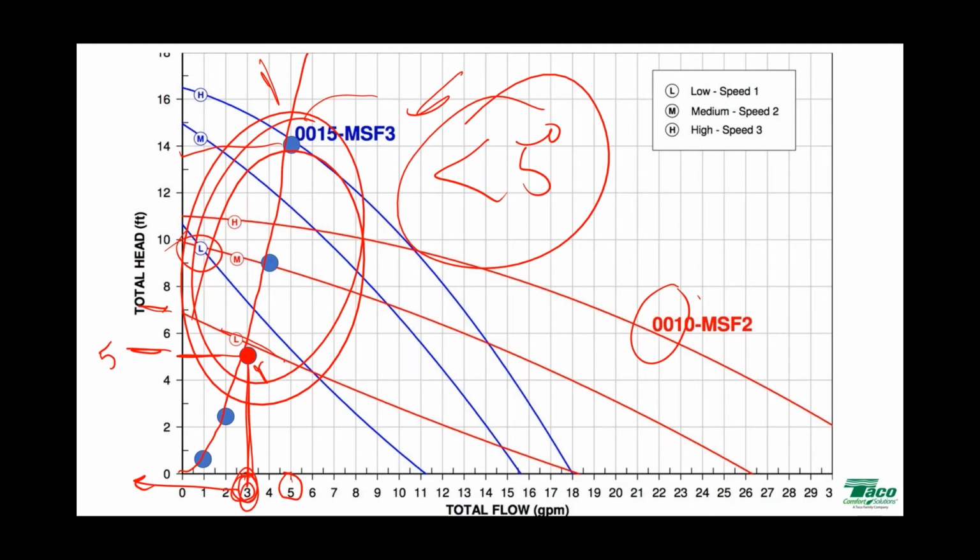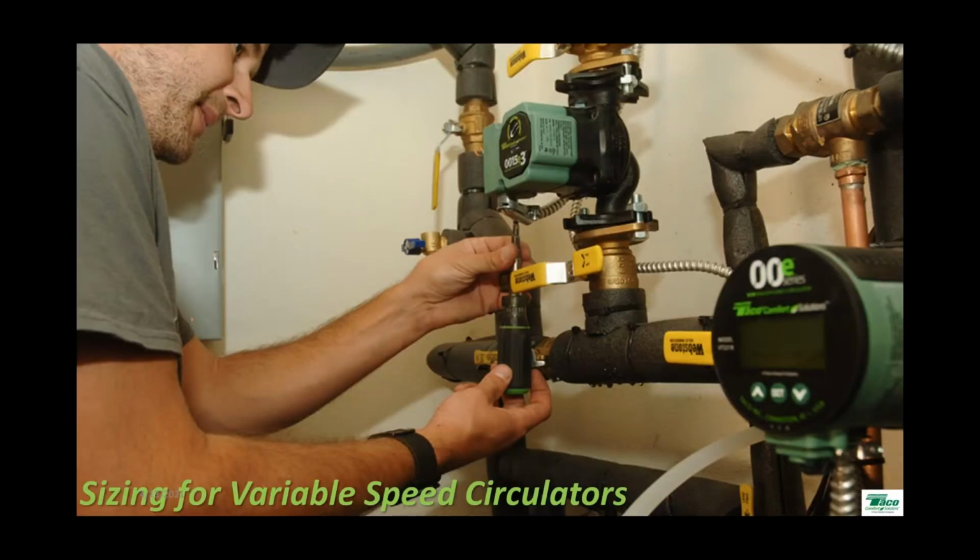And everything is true up until it comes to the point of choosing the circulator. Well, I use this circulator all the time because I get it for the best price and it's never failed me, and they always set them to high. So you're getting like 90% of the way there, and that last 10%, which is the most important 10%, we're basically not paying attention to. The circulator, as we said before, has more to say about the overall efficiency of the system and the long-term viability and performance of the system than we ever really gave it credit for. And for that, we thank ECM circulators.